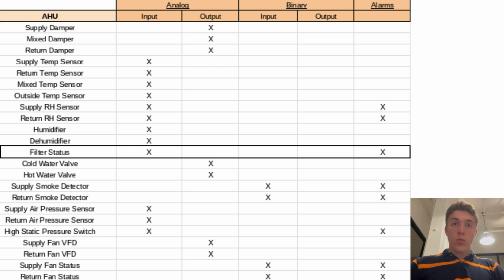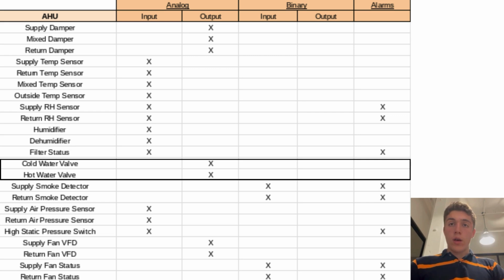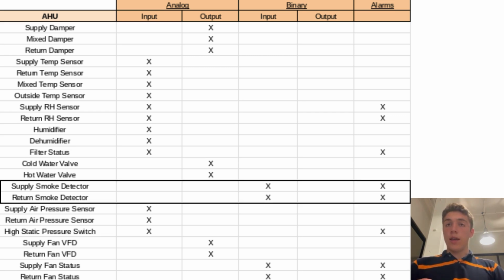Next, we have the cold water valve and the hot water valve. These control how much water goes into the cooling tubes that the air is blown over to keep the temperature of the air constant. Next, we have the supply smoke detector and the return smoke detector. Again, these are binary inputs because they either detect smoke or they don't.